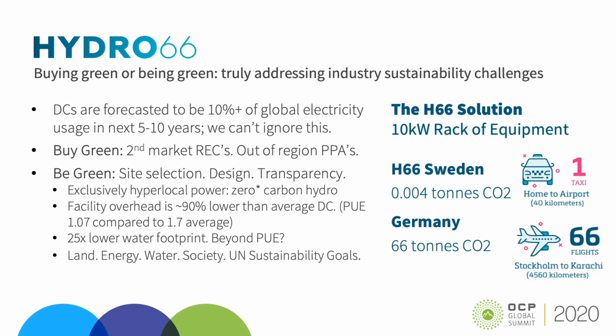Because of our design, only about 4 to 7 days a year do we actually need to physically cool the equipment. Most of the time we use free air with recycling, particularly in winter to stop the facility freezing rather than overheating. Our PUE is typically 1.07 compared to an average of 1.7—90% lower, or we use just 10%. Beyond PUE, we also use 25 times less water footprint compared to more traditional data centers.